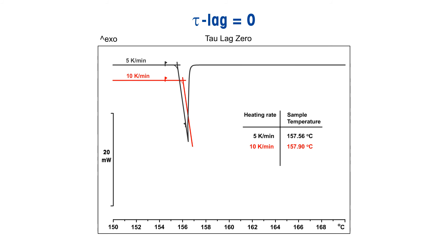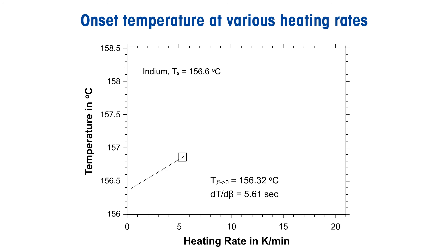DSC measurements of the same sample, for example indium, with different heating rates in an unadjusted instrument would show different melting onsets, but melting points should be heating rate independent.